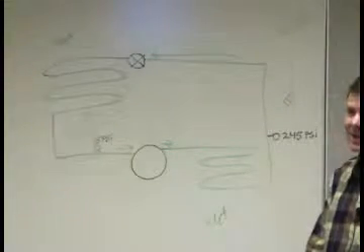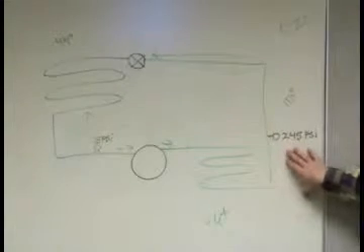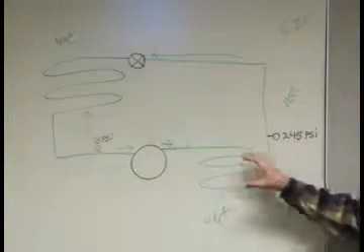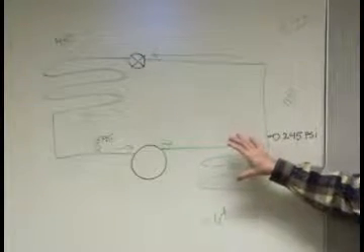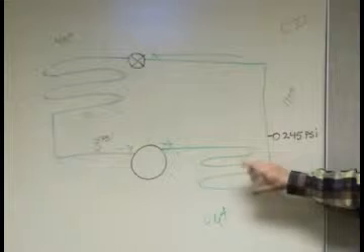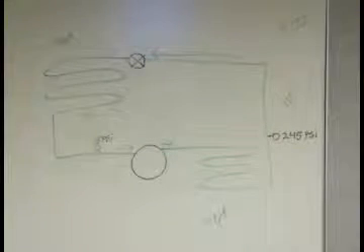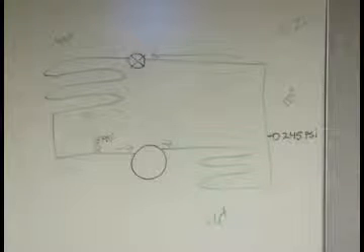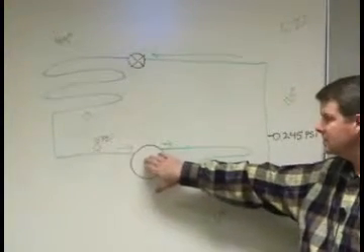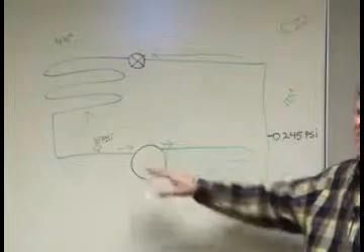It's like extra heat you get. In the summer, when you're pumping it up, that extra heat, you don't really want it. You want the pressure, not the heat. So you end up making your coil and the fan a lot bigger on the outside to get rid of that. So heating efficiency-wise, that's what makes heat pumps attractive, is you get a heat with all that energy that you're using in the compressor. A great deal of it anyway.